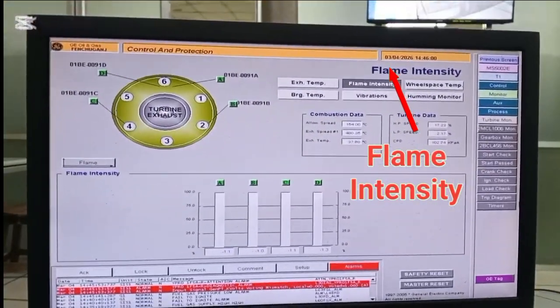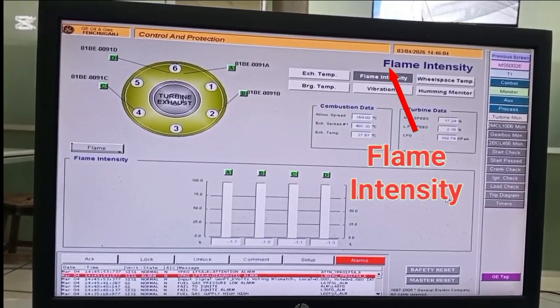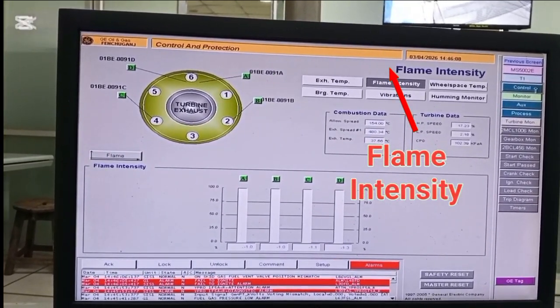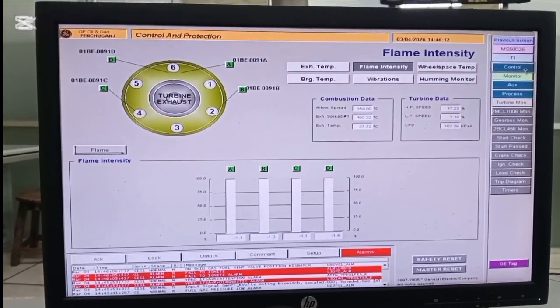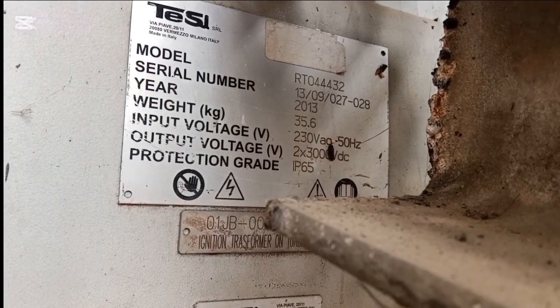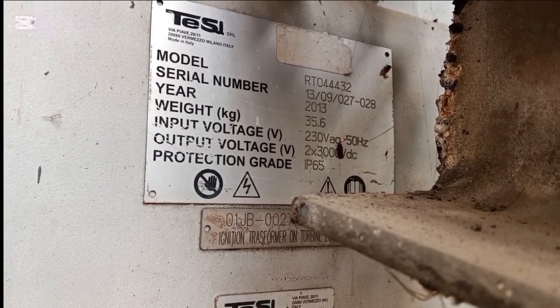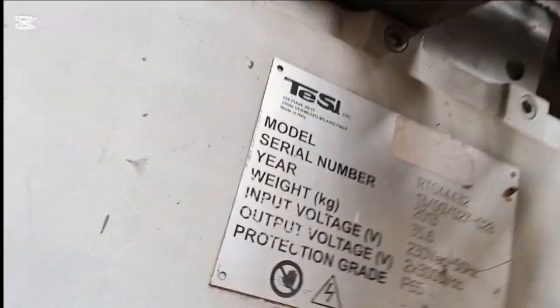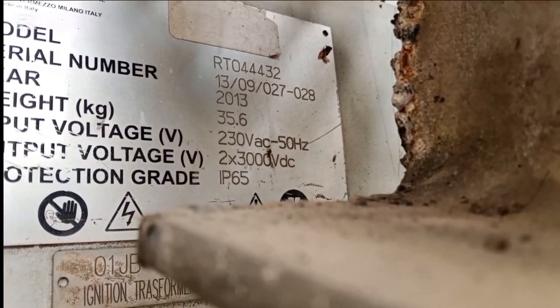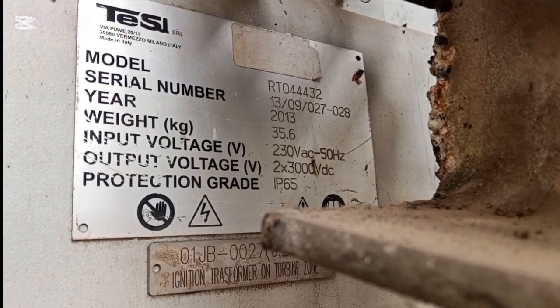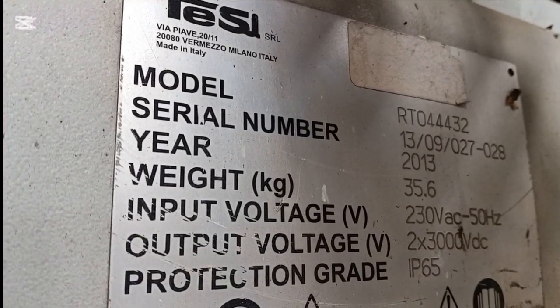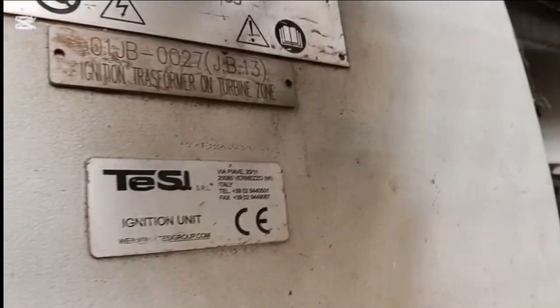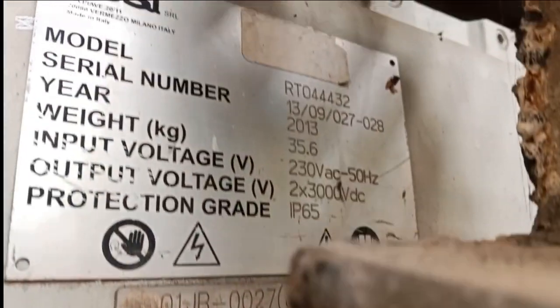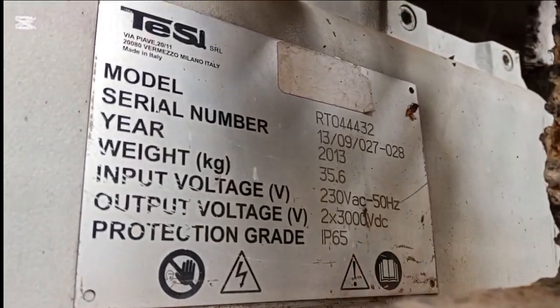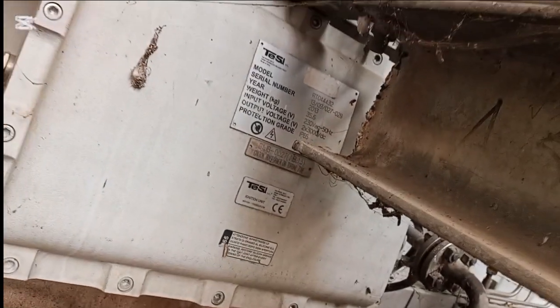At this stage, we again want to check the spark plug as well as the ignition transformer. The ignition transformer primary voltage is AC 230 volt, and its output voltage is 2 into 3000 volt DC. This is situated at the boiler, that is the gas turbine field side. This is the box, and here are its model number, weight, output voltage and input voltage. Everything is described here. Inside this box there are 2 transformers, and as the transformer output is AC voltage and the spark plug needs 3000 volts DC, here is a control circuit, and 2 capacitors are also used here.